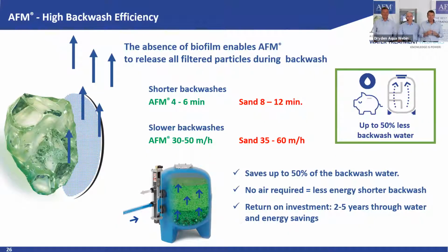You can do the math here. Typically we're talking about 50% backwash water savings. You do not need air scouring. So very important, no air blowers, a significant amount of energy savings. It makes the process much simpler and shorter, and this really speeds up your return on investment.